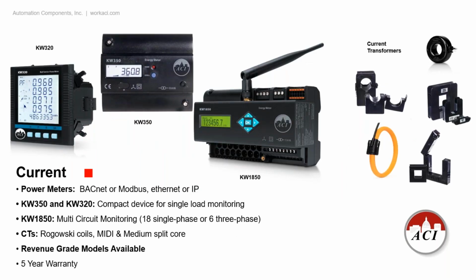Recently, we came out with power meters or kilowatt hour meters. We have 3 devices shown here. The KW350 is a 0.5% accuracy unit. The KW320 is kind of the all-in-one and a 0.2% accuracy unit. The KW350 is probably your best option in our marketplace where you're needing just BACnet or Modbus MSTP. If you're needing IP, that would be the KW320. Now the 1850 is a multi-circuit monitor. So that can do 18 single phase or 6 3-phase. The other 2 will do 3-phase power monitoring.